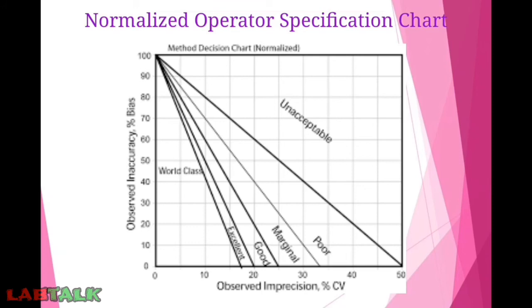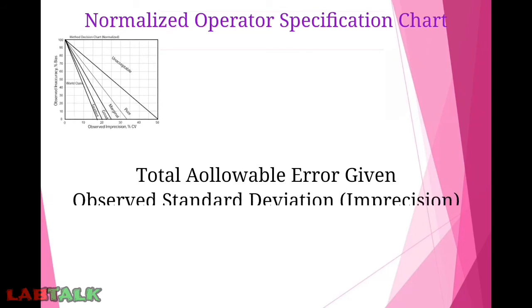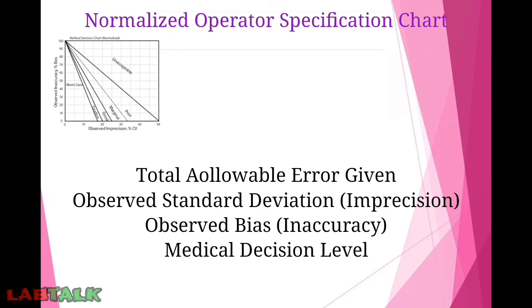The only difference is that the x-axis ranges from 0 to 50 and the y-axis ranges from 0 to 100. The y-axis represents observed inaccuracy (% bias) up to 100%, and the x-axis represents observed imprecision (%) up to 50%. Data required for plotting includes: total allowable error in actual value, observed standard deviation (imprecision) in actual value, observed bias (inaccuracy), and the medical decision limit.